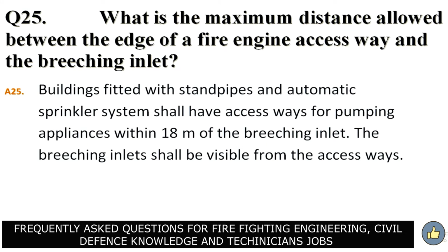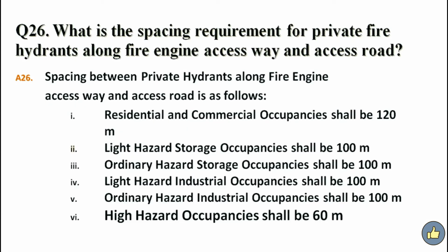What is the maximum distance allowed between the edge of a fire engine accessway and the breaching inlet? Answer. Buildings fitted with standpipes and automatic sprinkler system shall have accessways for the pumping appliances within 18 meters of the breaching inlet. The breaching inlets shall be visible from the accessways. What is the spacing requirement for private hydrants along fire engine accessway and access road?